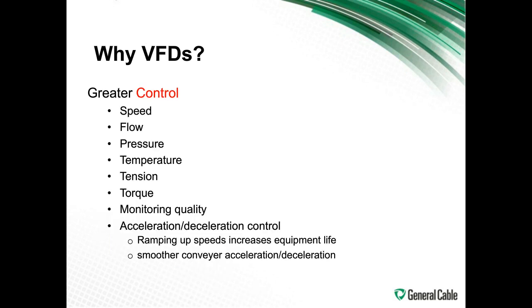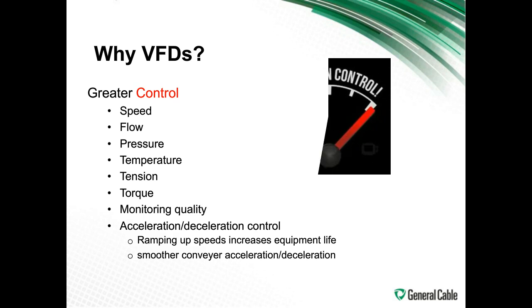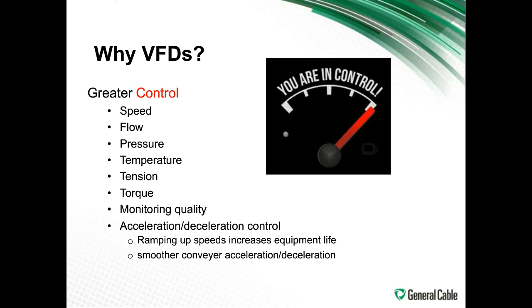Another reason is, along with the speed control, you have flow control, you have pressure control, temperature control, you can control the torque, the tension, you can monitor the quality, you can actually control the acceleration and deceleration and ramping up speeds. You have basically better control of your whole system using a VFD drive.